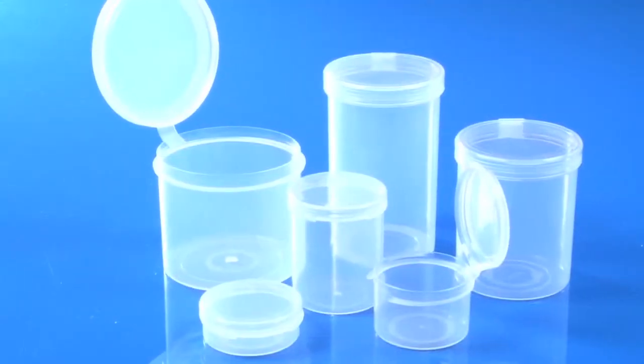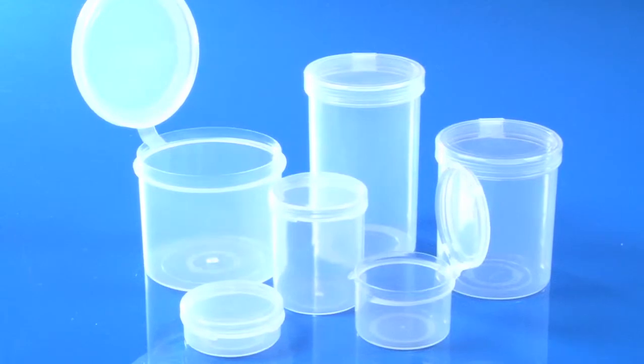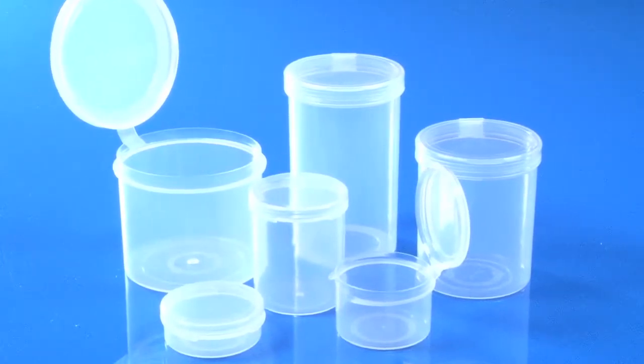Standard polymers like lab-grade polypropylene cannot handle the sterilization process and are left brittle and stained yellow. Instead, specialized PP gamma polymers are used to manufacture plastic containers engineered to withstand the gamma sterilization process. The material used at LA Container is a USP Class 6 highly clarified random copolymer resin designed specifically for the manufacturing of medical devices suitable for sterilization.